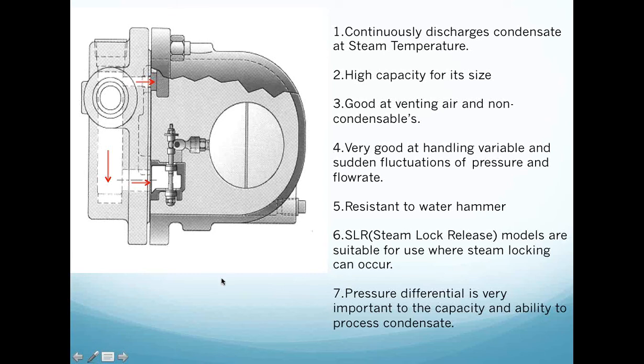They're very good at handling variable and sudden fluctuations of pressure and flow rate. The components are now very resistant to water hammer. The steam lock release design of this trap is suitable for applications like paper drying cylinders where steam locking can occur. And pressure differential is very important to the capacity and the ability to process condensate with this particular device.